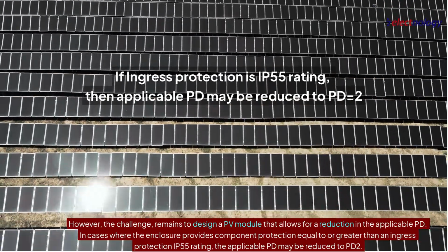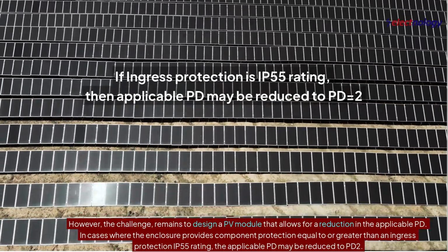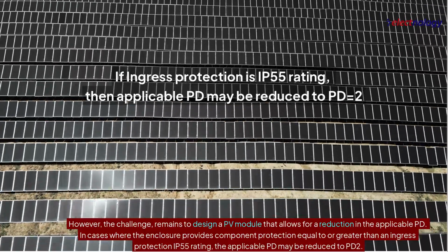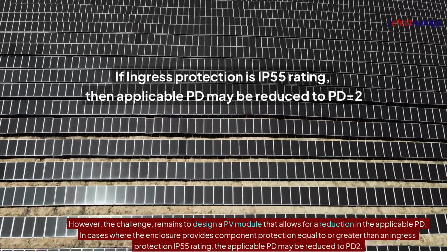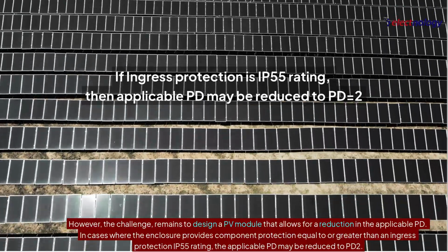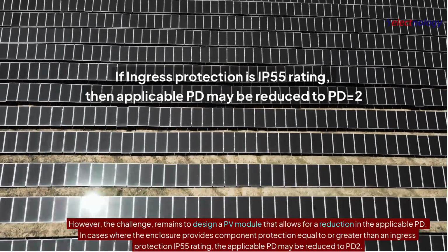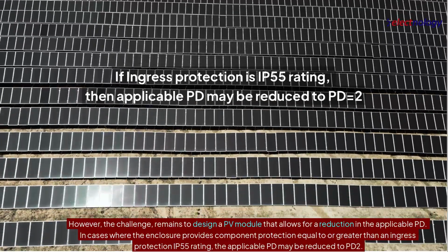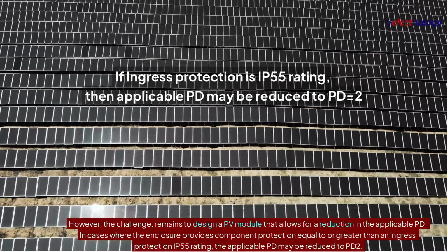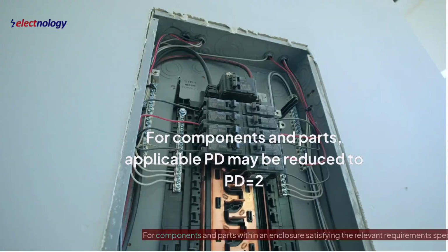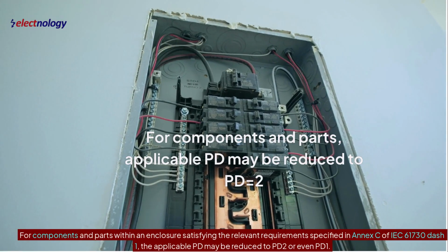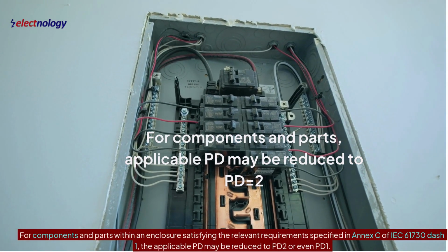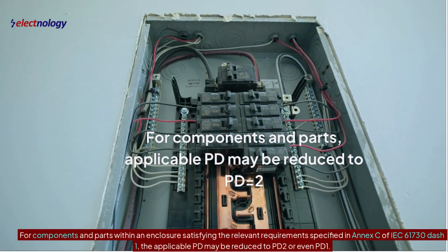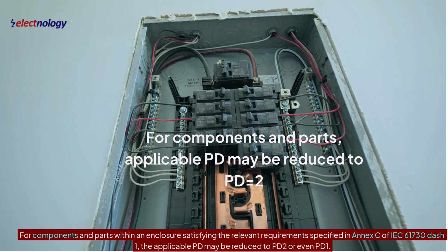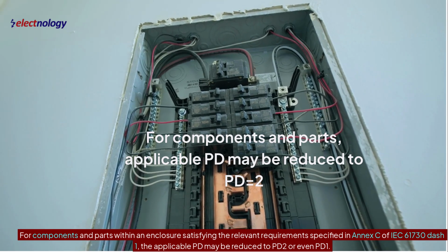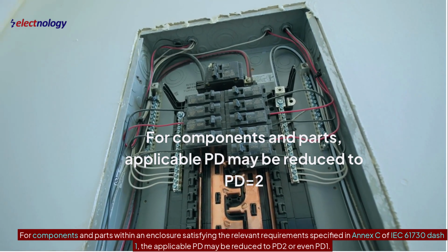However, the challenge remains to design a PV module that allows for a reduction in the applicable PD. In cases where the enclosure provides component protection equal to or greater than an ingress protection IP55 rating, the applicable PD may be reduced to PD2. For components and parts within an enclosure satisfying the relevant requirements specified in Annex C of IEC 61730-1, the applicable PD may be reduced to PD2 or even PD1.